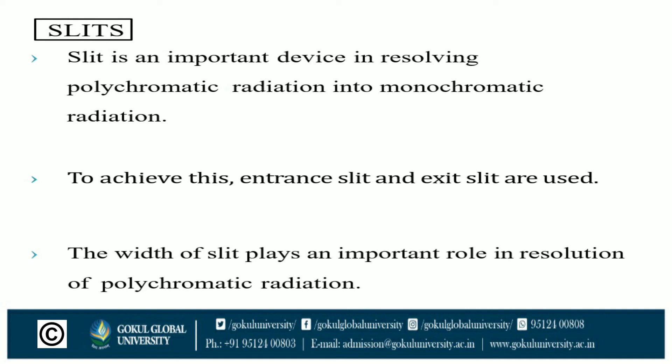Slits: a slit is an important device in resolving polychromatic radiation into monochromatic radiation. To achieve this, entrance slits and exit slits are used. The width of the slit plays an important role in the resolution of polychromatic radiation.